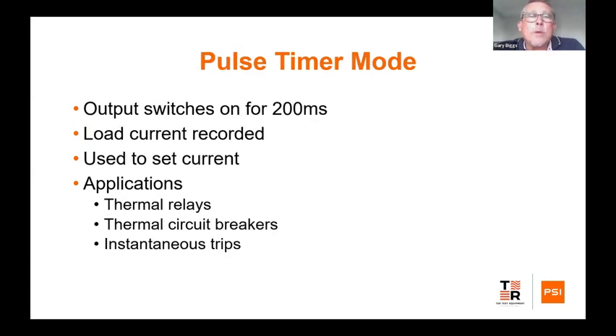We then have what we call the pulse timer mode, and that allows us to output and control the output so that the unit will only give you 200 milliseconds of current coming out of the tester. Now, we would use this for instantaneous trip type devices, or I would use this if I wanted to set my current through a thermal relay, but I didn't want to inject, mess about for a couple of seconds trying to get the right current, because as I'm injecting current into a thermal relay, it will be warming it up. So when I then go to test it, you've already warmed the relay up. By giving you that ability to limit that current to 200 milliseconds, I can find the level, let's say that I want 10 amps. I can find my level where it is at 10 amps. And then I can turn it into the normal timer mode, output that current, and I know that that thermal relay hasn't been warmed up too much to interfere with the results that I want to take.